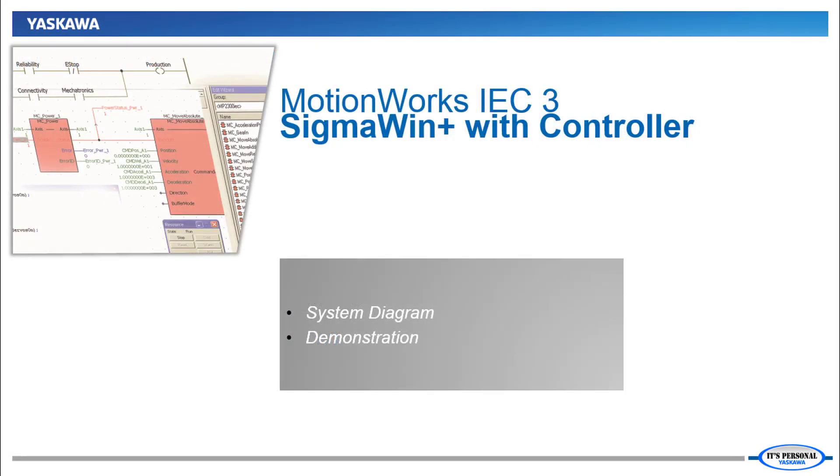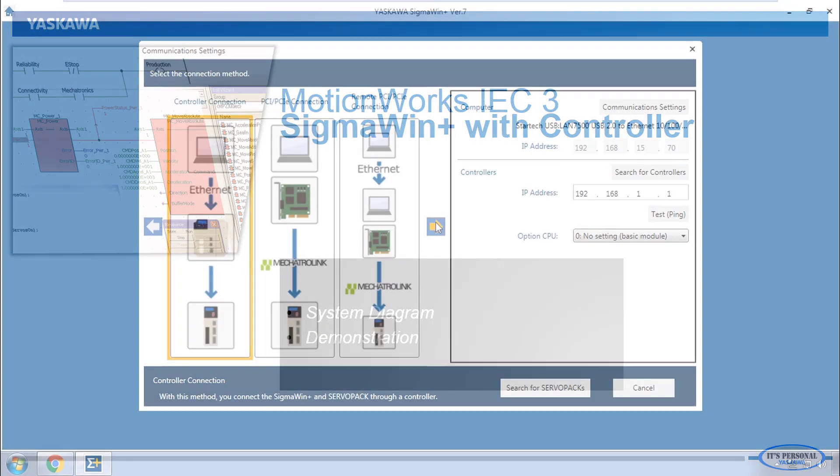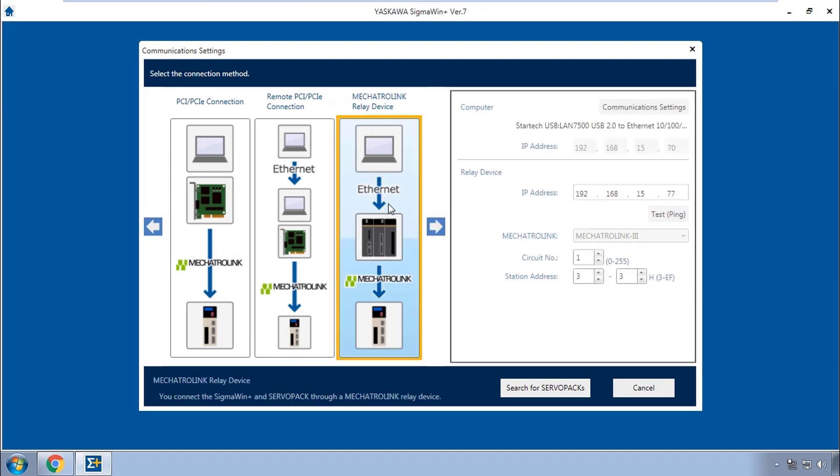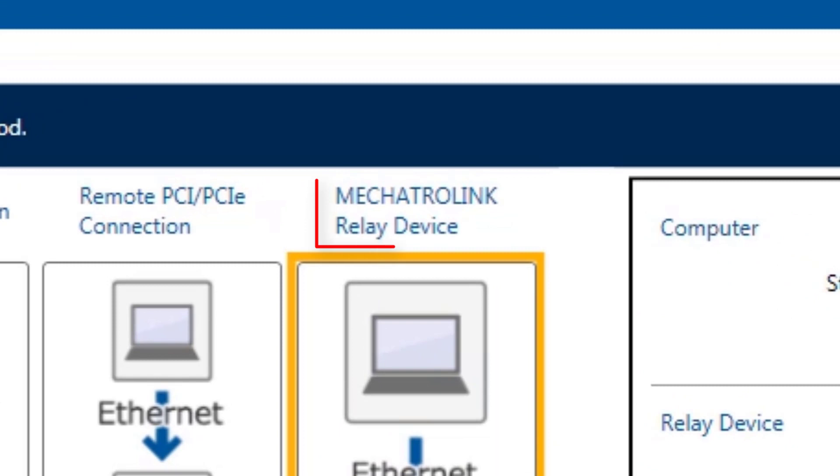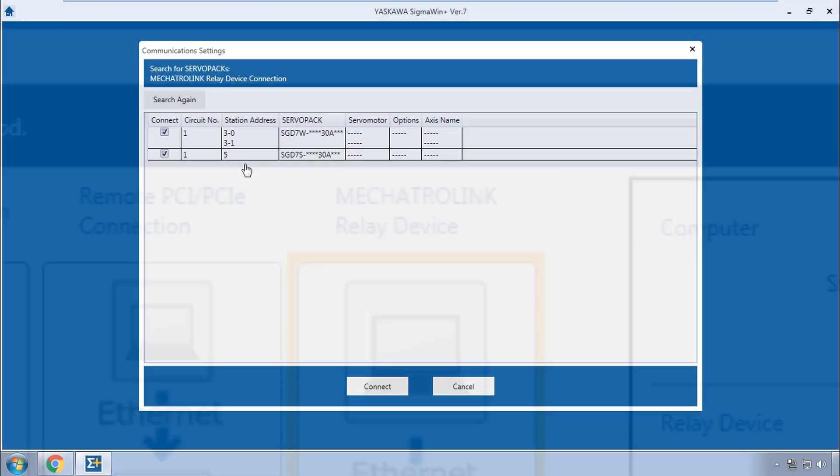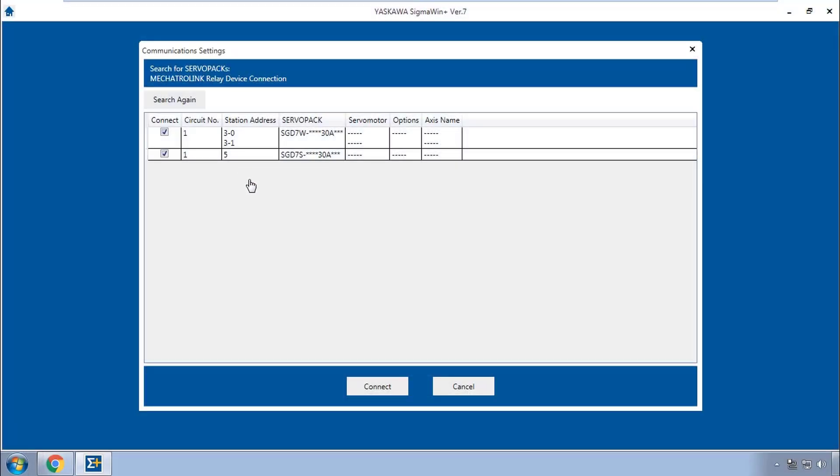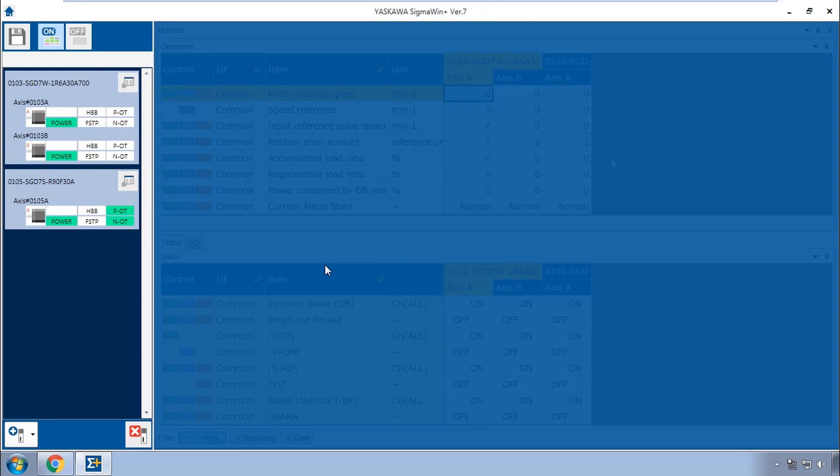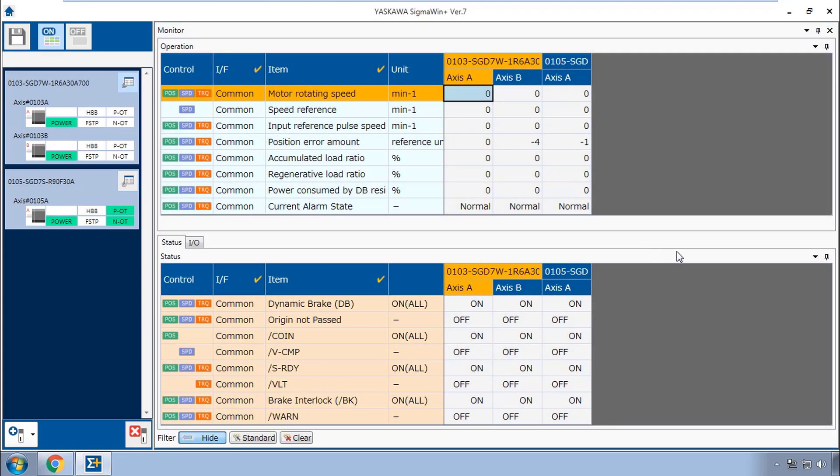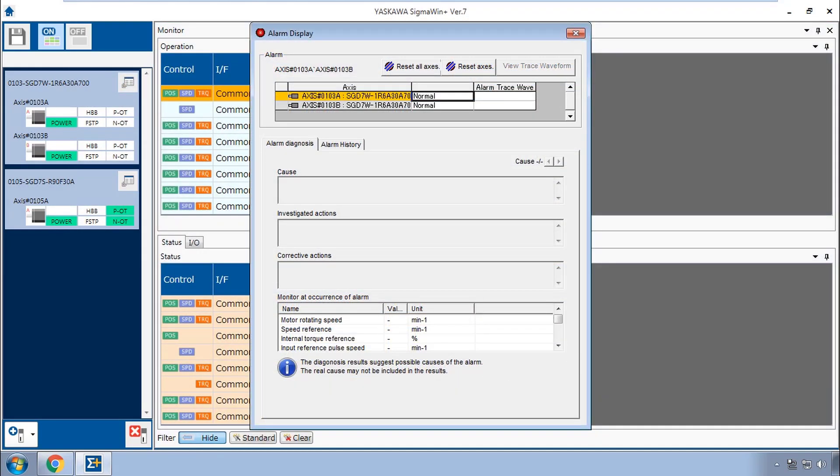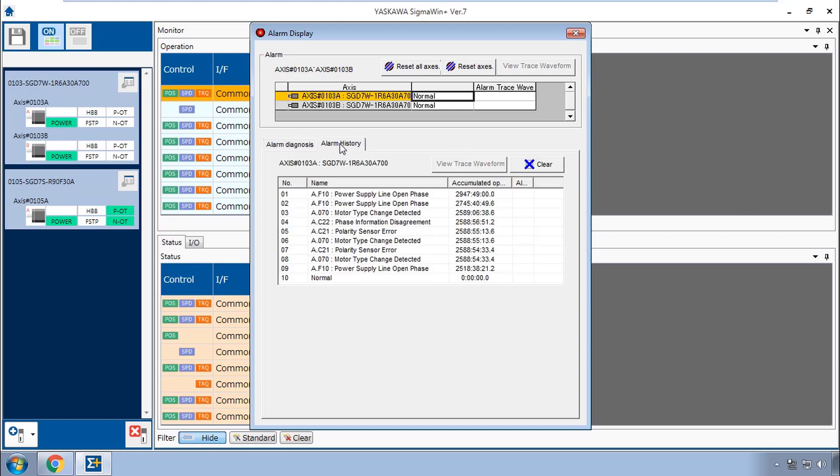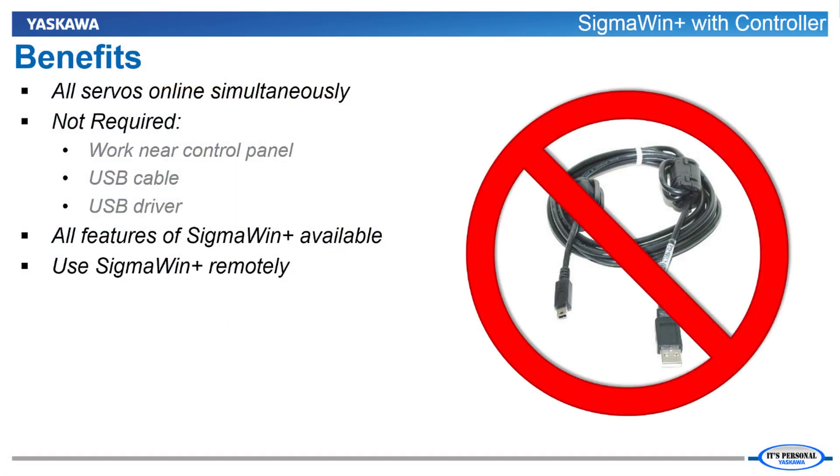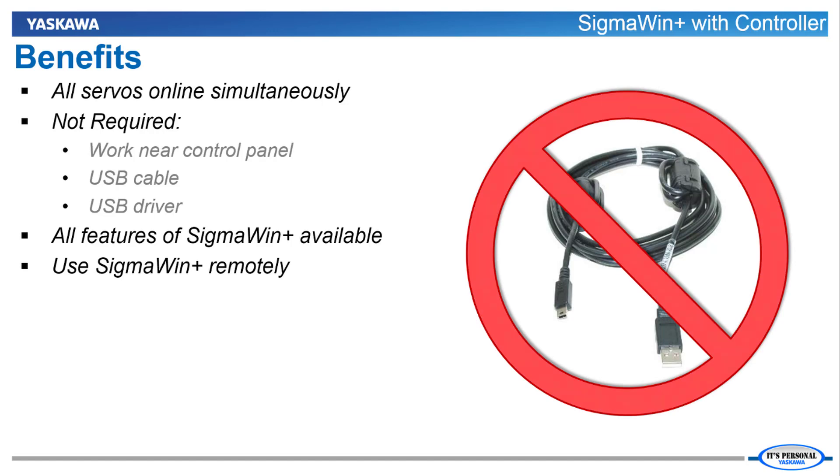Here's a quick preview. If your PC has Ethernet communication to the controller, the Sigma Win Plus 7 connection option Mechatrolink relay device allows communication to all servos simultaneously. Status information can be displayed for all axes at once and you can quickly examine and troubleshoot a particular axis more closely. You don't need a USB cable or driver, just your PC and Ethernet connection.